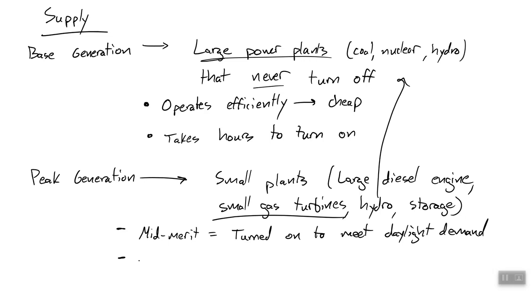And then we have peaking plants, which are the smallest, and most importantly, the least efficient. But they are fast to turn on. You could turn this thing on in a matter of seconds to minutes, when you see that the grid is starting to get stressed and the frequency is dropping. But an important thing here is least efficient. We don't want to run these peaking plants, but we have to because the grid must be reliable.